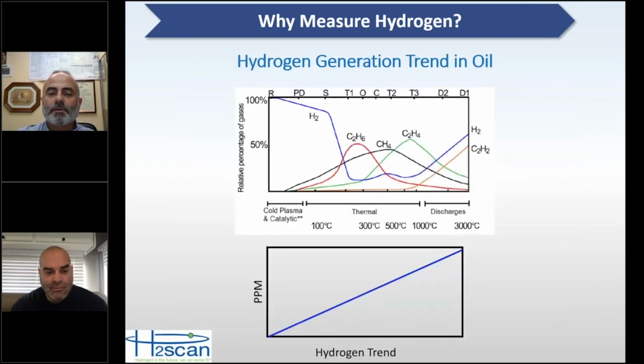And so if you look at just your hydrogen trend, it will continue to increase on somewhat of a linear basis if you just continue to increase the temperature of the problem in the transformer. And so again, the faster or the hotter the issue in the transformer, the faster you're going to generate hydrogen. And so hydrogen is a great indicator of a significant issue in the transformer.